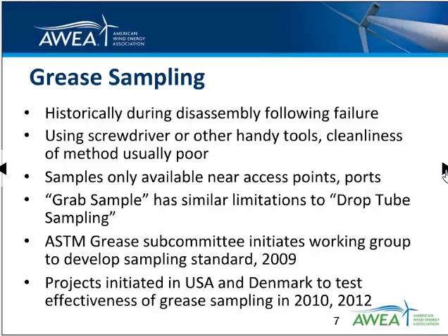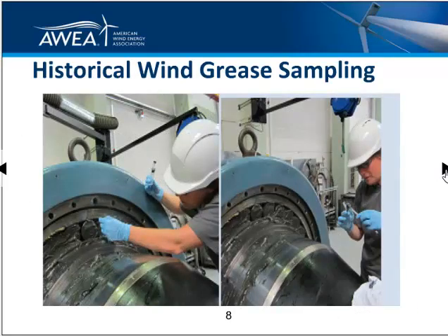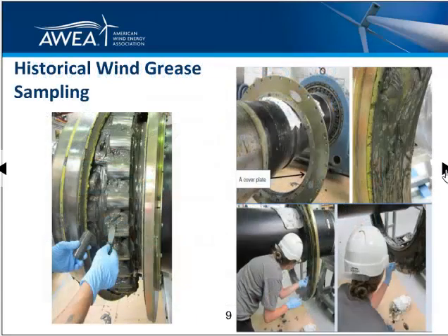In the same timeframe, projects were initiated in the U.S. and in Denmark to test the effectiveness of grease sampling in the 2010 to 2012 timeframe. Historically, you get the bearing back to the shop, disassemble it at least partially, and reach inside to try to extract the grease. Here's a photograph from a major wind OEM workshop where the technician has partially disassembled the bearing and is grabbing grease from between the rollers, with the idea that grease from those locations will have the most information.